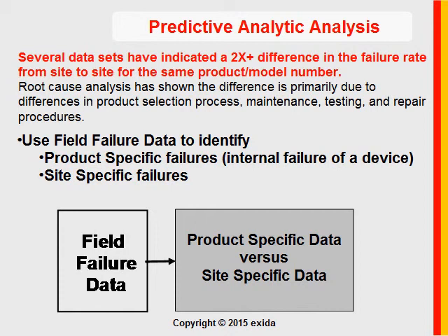We also use predictive analytics to identify product-specific failures versus site-specific failures. And what I mean by that is, I find it a fascinating subject. Several data sets, once the data collection process was validated, have indicated a 2x difference in the failure rate from site to site for the same product model number.